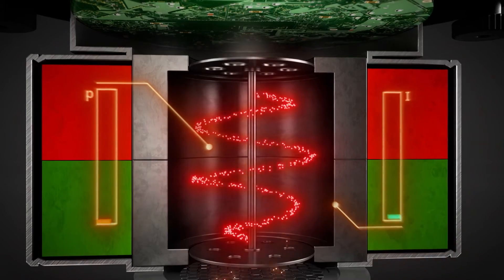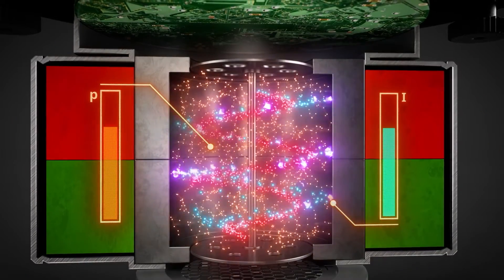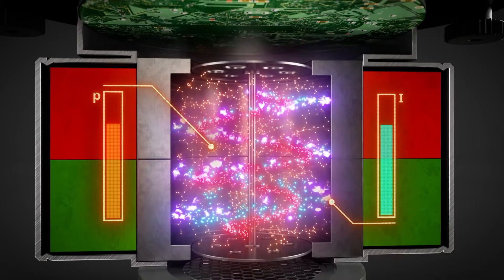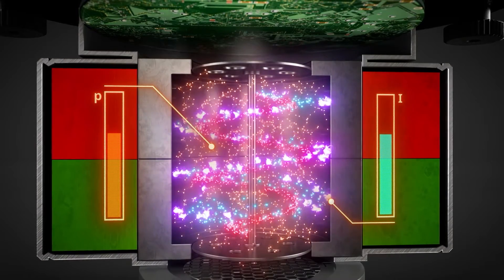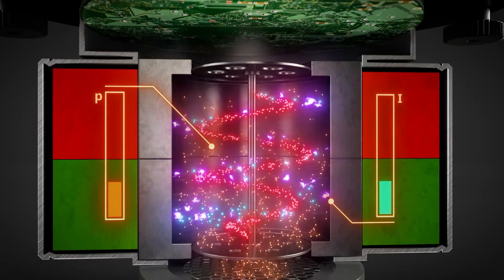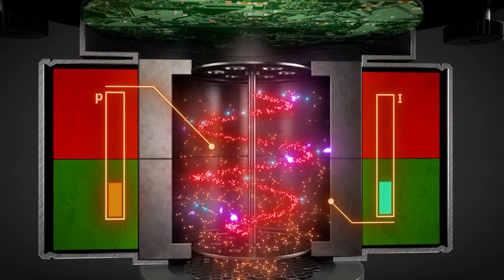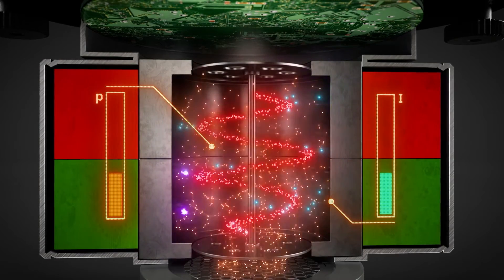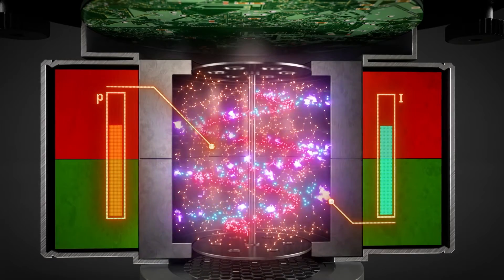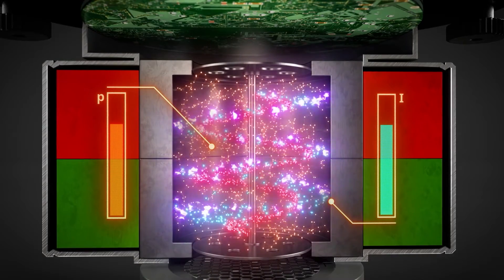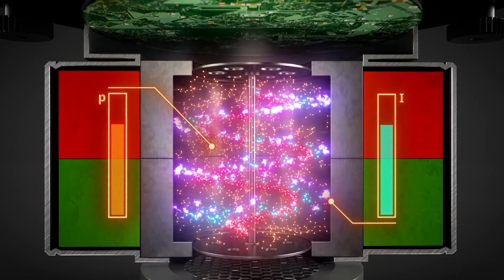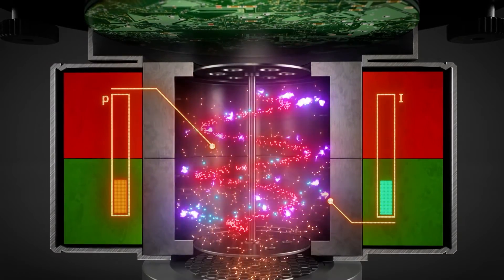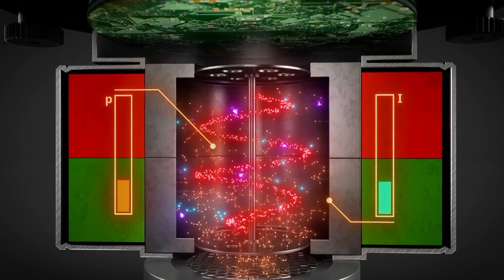As the pressure of the gas increases, so does the number of molecules in the chamber. The possibility for collisions is therefore higher. As a result, more cations and more electrical signals are generated. This means that the current and the pressure are proportional to one another, so the pressure can be determined by measuring the current.